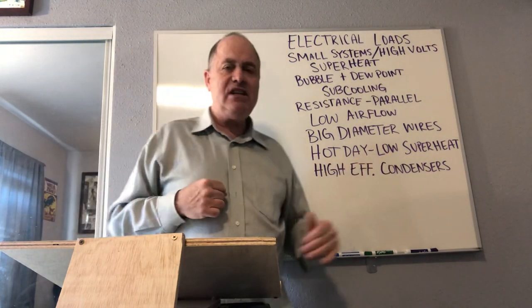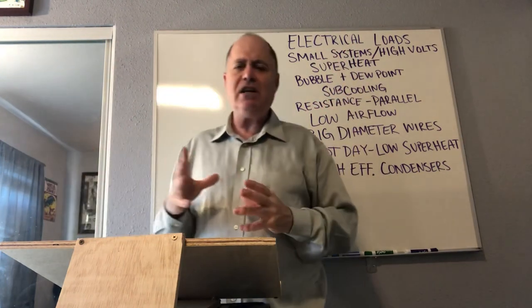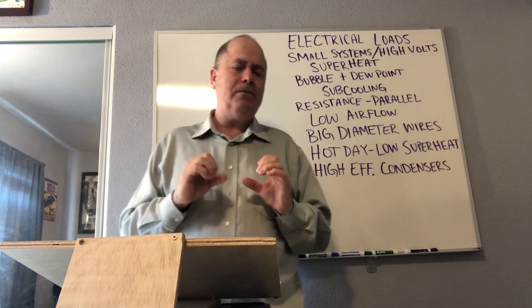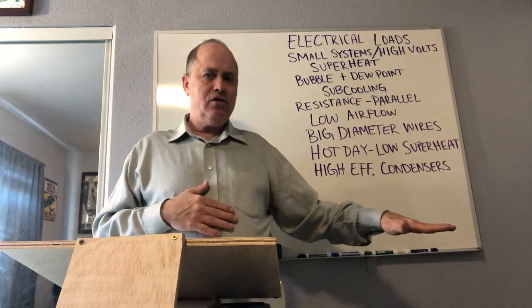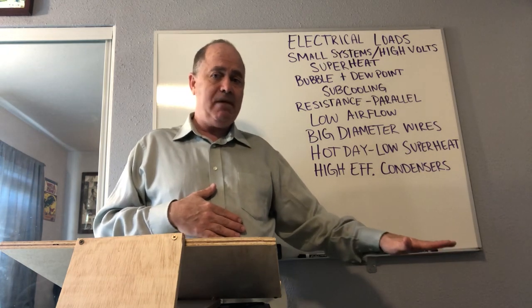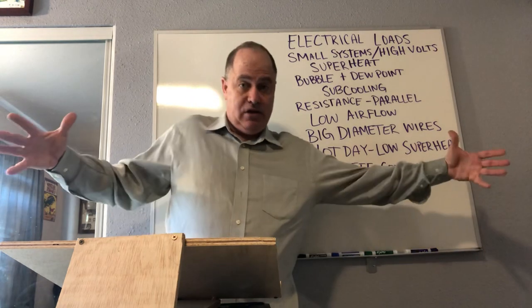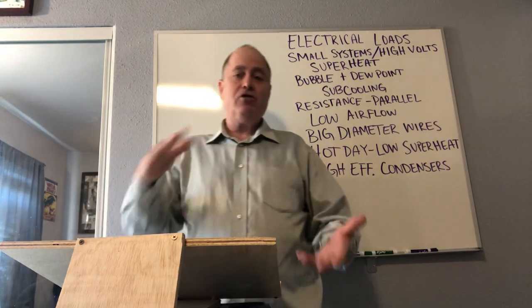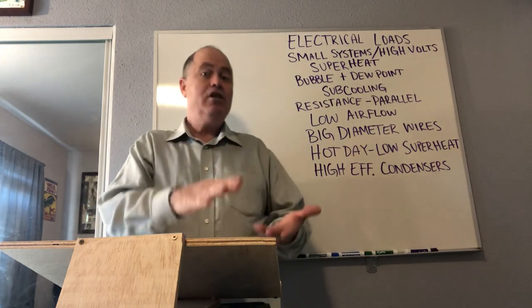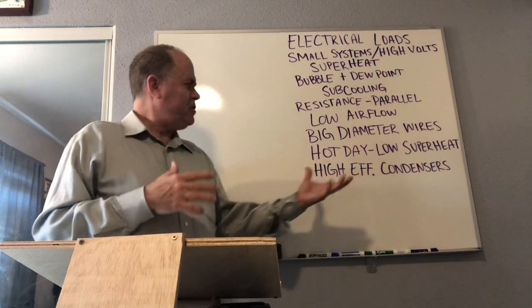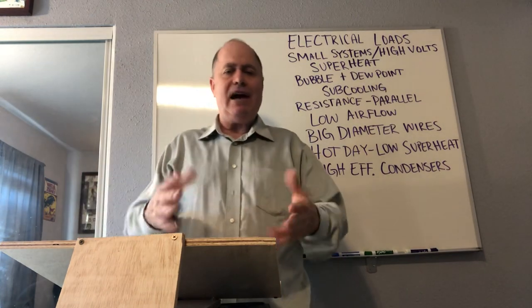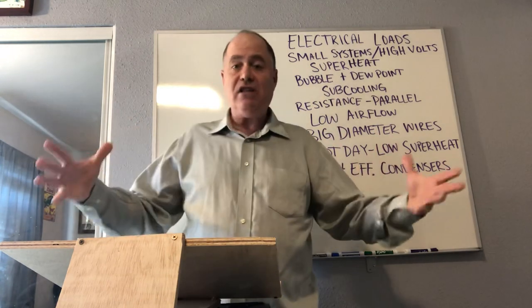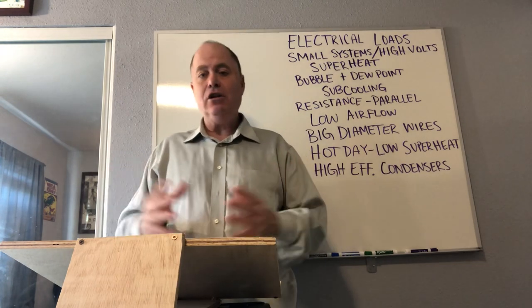High efficiency condensers are actually bigger. Usually we think high efficiency things get smaller — especially with computers and electronics and communication, everything gets smaller and smaller. But 20 to 25 years ago, a 5-ton condensing unit would be a certain size; now a 5-ton condensing unit is much larger, because you need more surface area. The more surface area, the more heat you can get rid of in the condenser, the lower your head pressure, the lower your compression ratio, the lower your amps, and the more efficient the condensing unit is. So high efficiency condensers for the same tonnage are actually bigger — the opposite of what you might think — because you need the surface area for heat transfer. That concludes the opposite lecture.